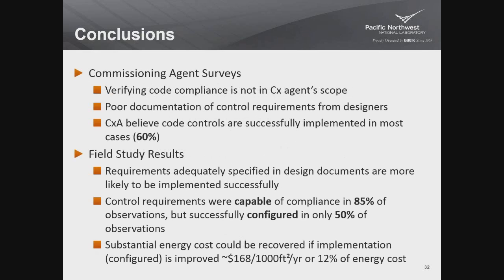Some of the big takeaways here, I think, on the commissioning agent survey, it's clear that verifying code requirements is not considered to be in the commissioning agent's scope for the majority of commissioning agents. Poor documentation of control requirements from designers is one of the things that leads to problems. But commissioning agents feel that the controls are being successfully implemented in most cases, 60%, more than half of cases, they feel that code control requirements are being successfully implemented. And now the field study.